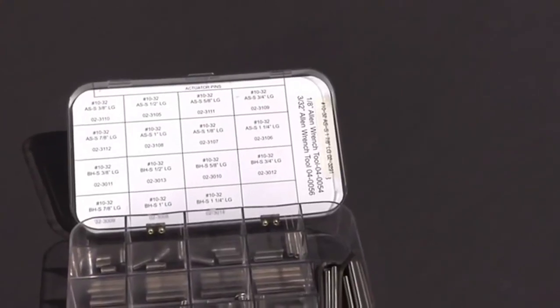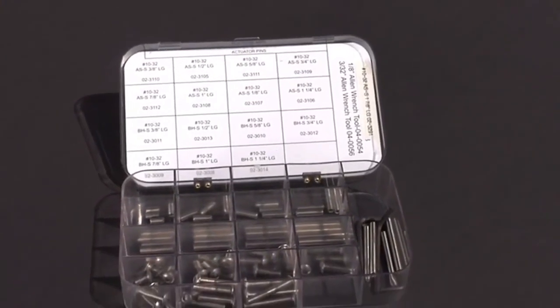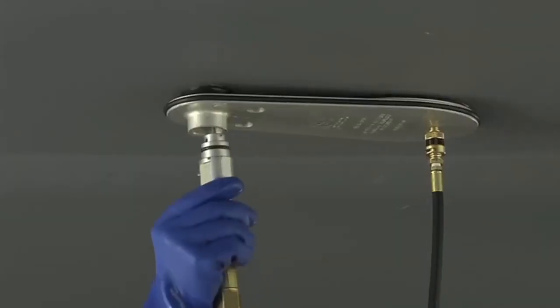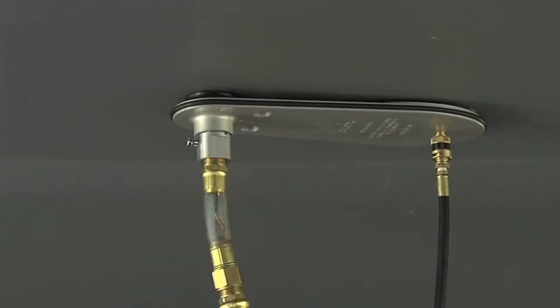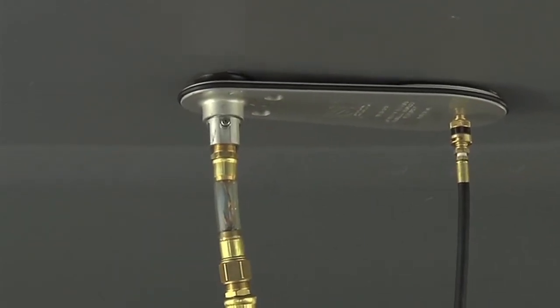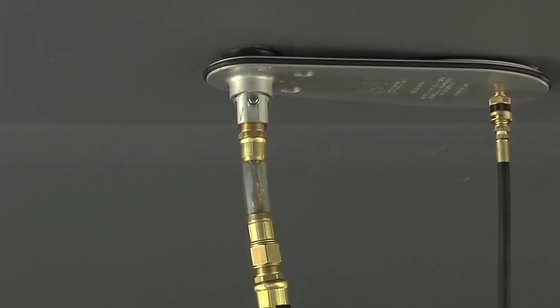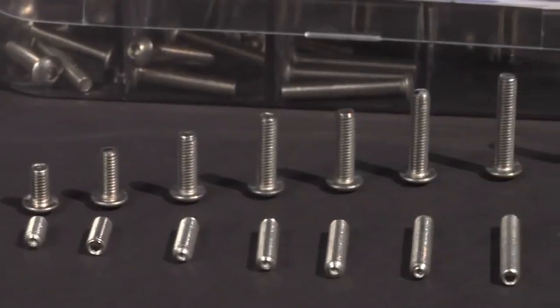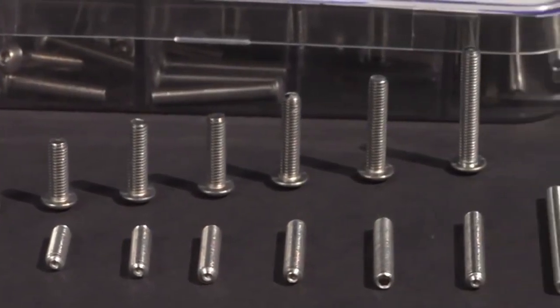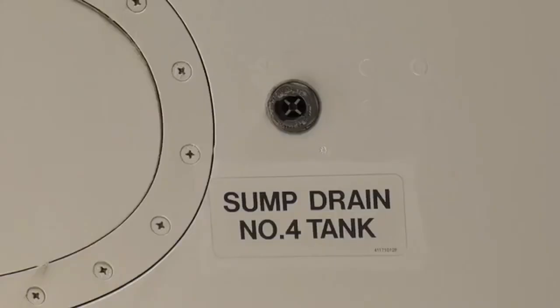Refer to the manual to determine proper fuel probe pin length. The ideal probe pin is long enough to fully engage the sump valve, but not so long that damage or jamming of the valve can occur. The rule of thumb is to select the shortest pin and work up to a pin that allows the fuel to flow well. It is likely that this same pin length will be required at this sump location on all of the same aircraft model.